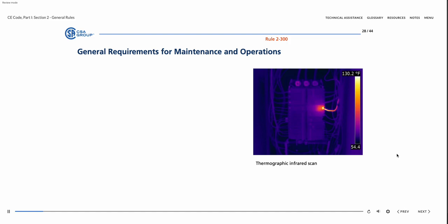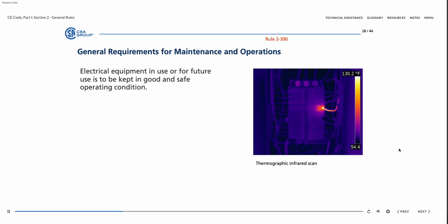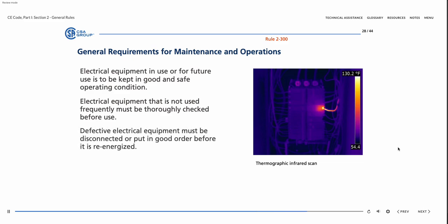General requirements for maintenance and operation require that electrical equipment in use or for future use is kept in safe operating condition. This includes the use of thermographic infrared scans to determine the condition of conductor terminations on a circuit breaker. Electrical equipment that is not used frequently must be thoroughly checked before use. Defective electrical equipment must be disconnected or put in good order before it is re-energized.